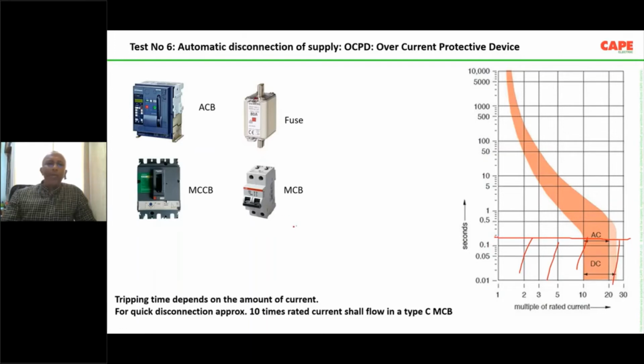Now imagine you have a type C MCB. The approximate current required for the MCB to trip is something about 10 times. A 63 amps MCB requires 630 amps to trip. The fault current shall be minimum 630 amps to trip. Similarly, if you have a type D MCB, the current is not 10 times, it is 20 times. So 1200 amps current is required to trip the MCB.